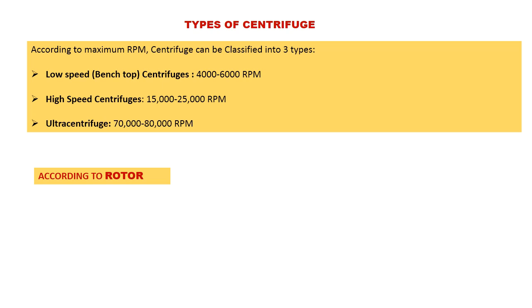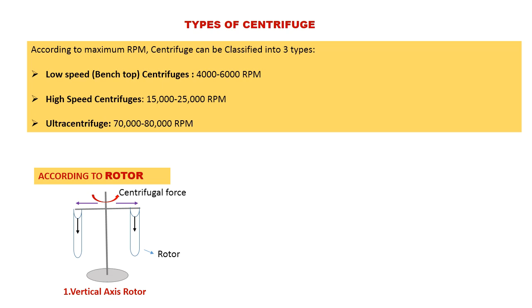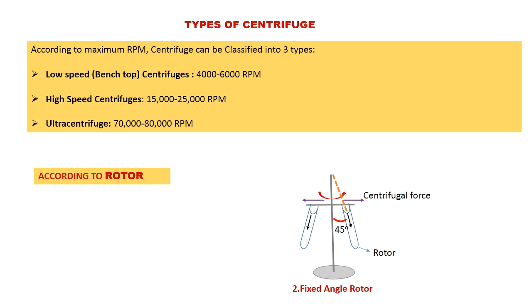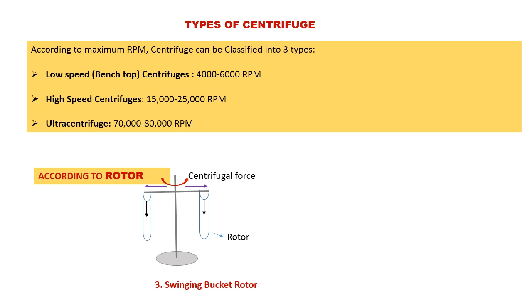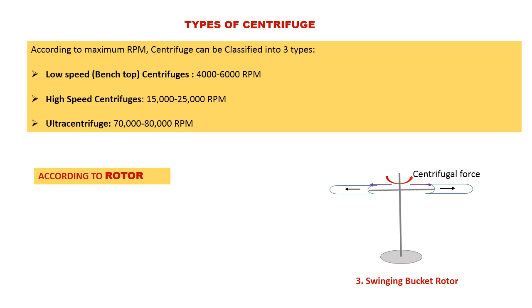According to the types of the rotor, the rotor may be of three types. First category is the vertical axis rotor, where the rotor is lying parallel to the axis of the motor. Second one is the fixed angle rotor, where the rotor lies at a fixed angle of 45 degrees to the centrifuge. And the third one is the swinging bucket rotor. Initially, it is lying parallel to the motor, but as soon as it starts rotating, it will shift to a position perpendicular to the motor. So this is the swinging bucket rotor.